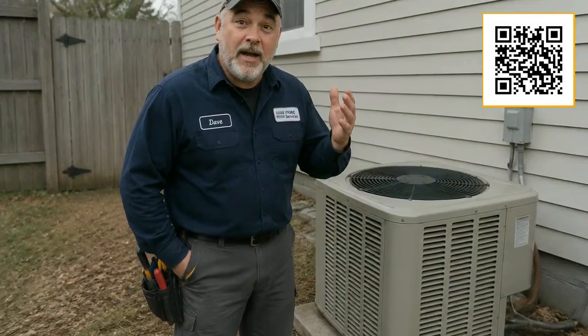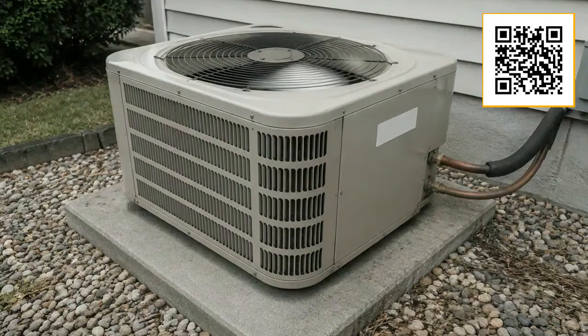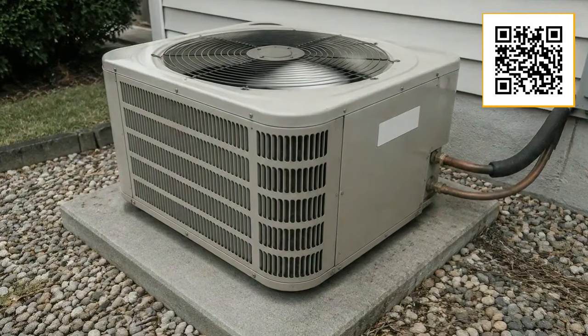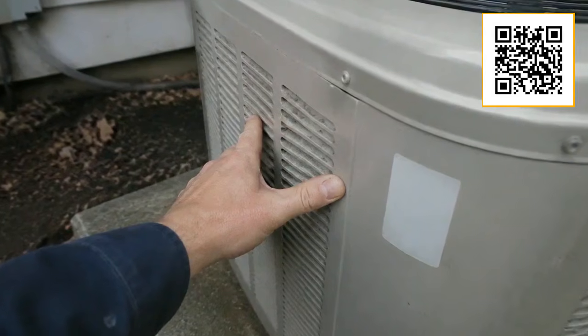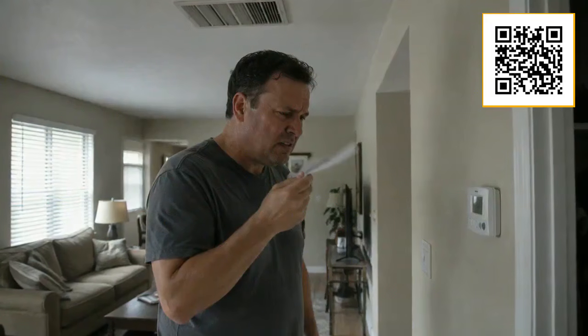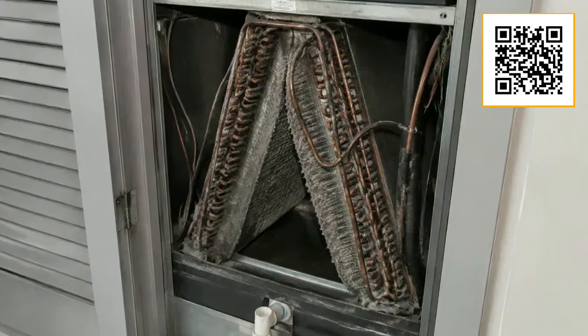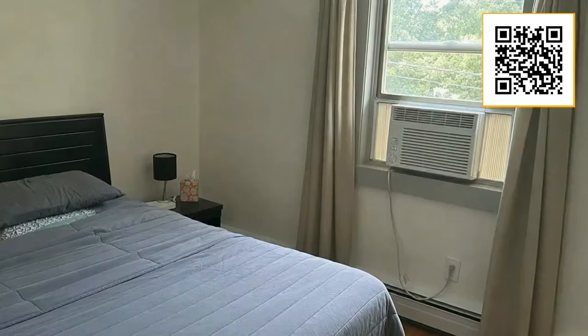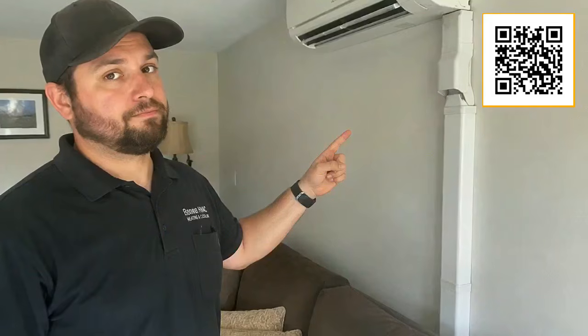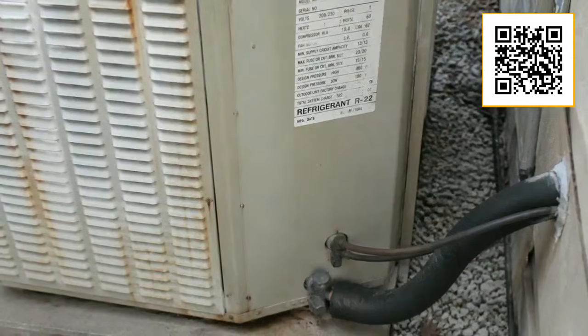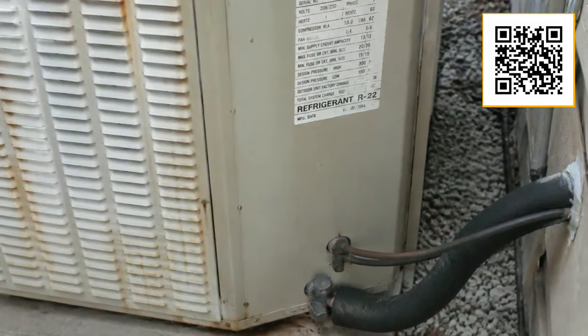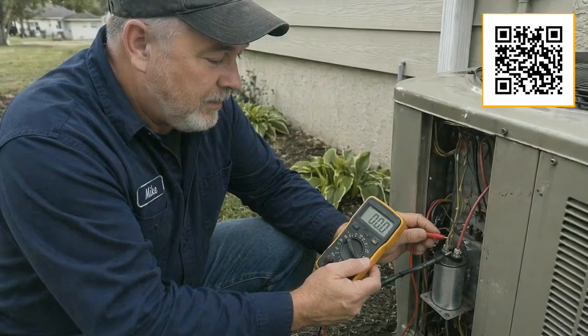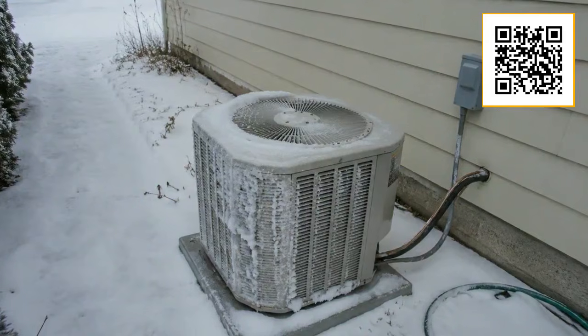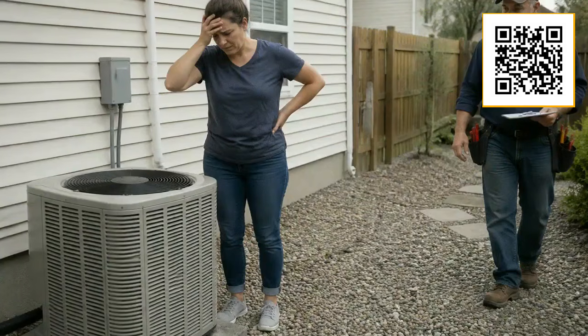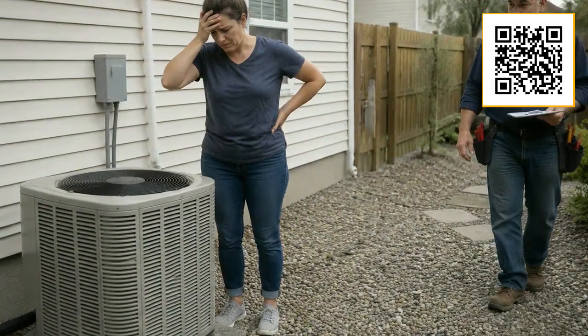Let me pull this all together for you. The units I see fail the most are not always old. They are oversized units that short-cycle themselves to death, cheap builder-grade equipment that has no margin for error, single-stage units running in climates that demand more, systems with dirty coils that nobody ever checked, window units asked to do a central system's job, mini splits that were installed carelessly, old R22 systems with limited repair options, units with worn capacitors that were never caught, heat pumps struggling through winters they were not designed for, and systems that simply never saw a technician until the day they quit.